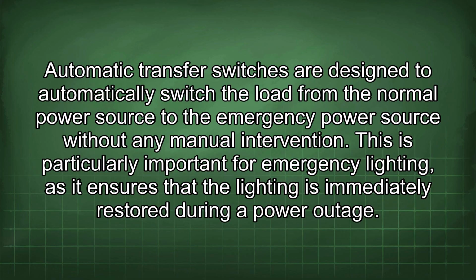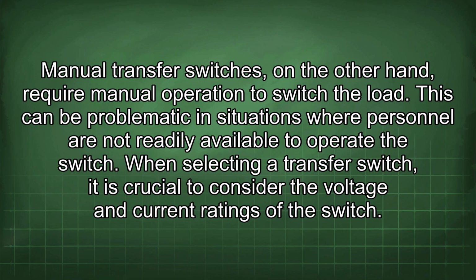Automatic transfer switches are designed to automatically switch the load from the normal power source to the emergency power source without any manual intervention. This is particularly important for emergency lighting as it ensures that the lighting is immediately restored during a power outage. Manual transfer switches, on the other hand, require manual operation to switch the load. This can be problematic in situations where personnel are not readily available to operate the switch.